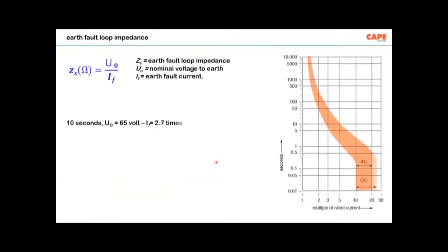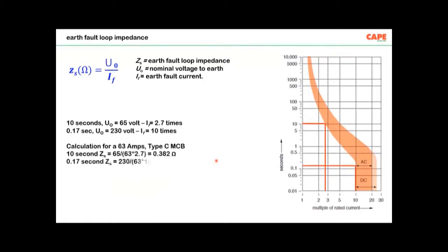Now, what is fault loop impedance? Basically, the calculations are given in the standard. I don't want to explain the calculations to you because most of you know it very well. The impedance of that particular circuit decides the amount of the fault current, which decides the disconnection time.